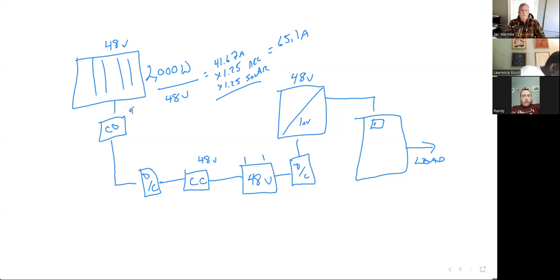I need to multiply that times 1.25, which is the NEC safety factor, and times 1.25 again for solar variability. So 41.67 times 1.25 times 1.25 equals 65.1 amps. Looking in the book on page 104 to see what size wire I need to handle 65.1 amps, I'm going to need 4-gauge wire.